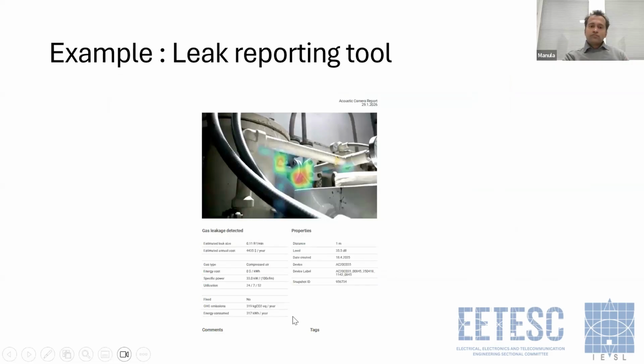And when it comes to leaks, most of the time users want to report these leak cases, because multiple leaks can be detected during one inspection round. Users can simply take snapshots and transfer them into this tool, and it will produce a report on this inspection round, which can be forwarded to the maintenance manager or whoever is responsible. So it provides an easy facility for reporting these leaks. In this example, it gives the estimated leak size, estimated cost, and even how much greenhouse gas emissions can be reduced by fixing this leak. That kind of data we can generate by using these offline tools.